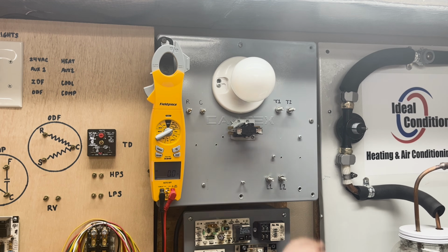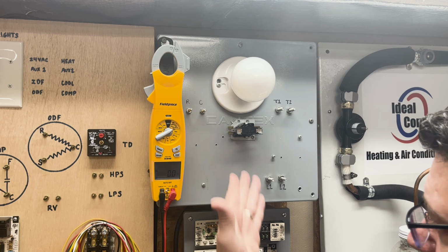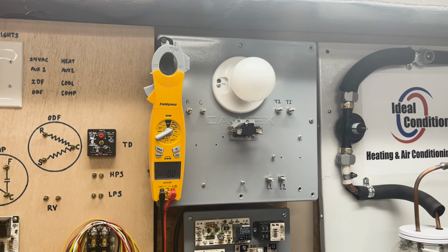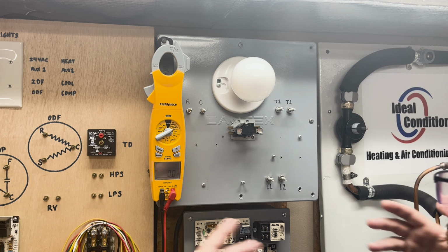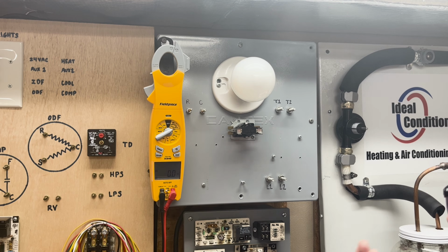It's very good if we wanted to use this as a blower relay to control our blower. Many manufacturers have done it. As an example, it's been used in Goodman for a very long time. What they were trying to do is get as much efficiency out of their evaporator coils as possible. If we can let that blower not come on immediately, then we can allow so much liquid refrigerant to flood the evaporator coil, making it nice and frosty cold. Then when that fan finally comes on within about 12 to 15 seconds or whatnot, it's more comfortable.